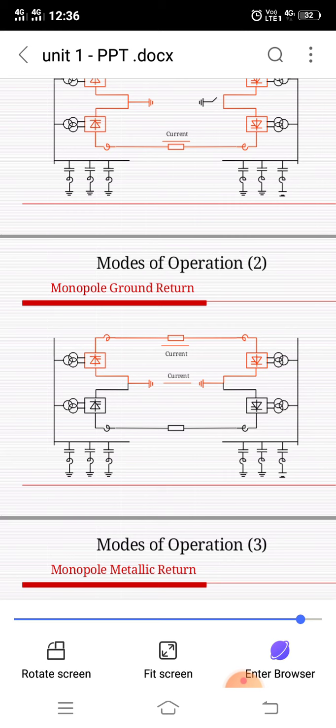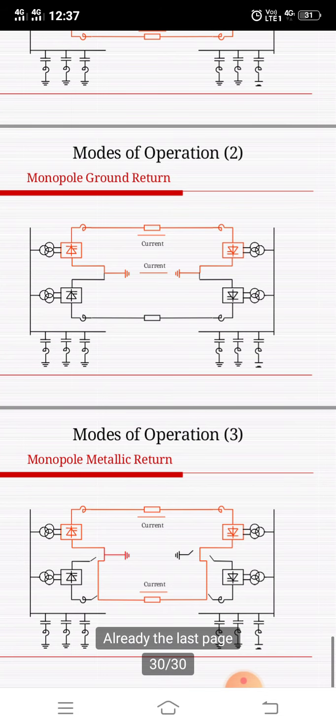When the firing delay is greater than 90°, the negative voltage-time areas dominate and the polarity of the average direct voltage changes. For this physical reason, the direction of the current does not change, because the thyristor valve conducts current only in one direction. When the direction of energy flow is reversed, the delivery changes to the supply side. The rectifier becomes an inverter which delivers energy to the AC network. Then the average value of the direct voltage as a function of the firing delay is given for each mode of operation.